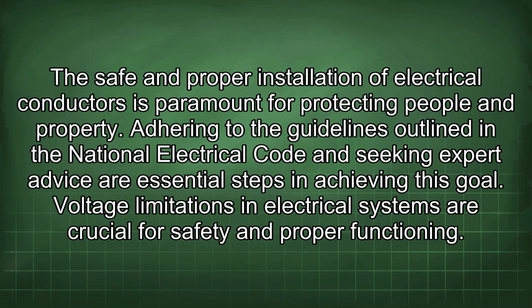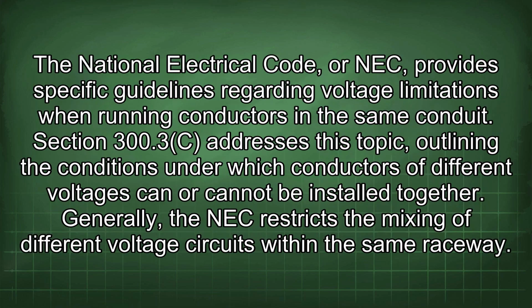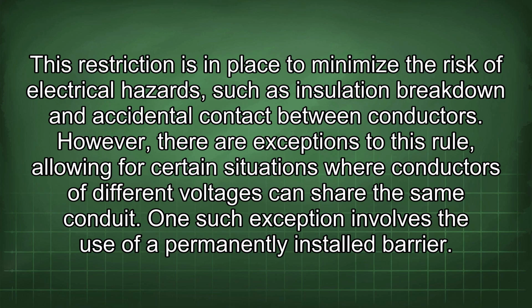Voltage limitations in electrical systems are crucial for safety and proper functioning. The National Electrical Code, or NEC, provides specific guidelines regarding voltage limitations when running conductors in the same conduit. Section 300.3c addresses this topic, outlining the conditions under which conductors of different voltages can or cannot be installed together. Generally, the NEC restricts the mixing of different voltage circuits within the same raceway.